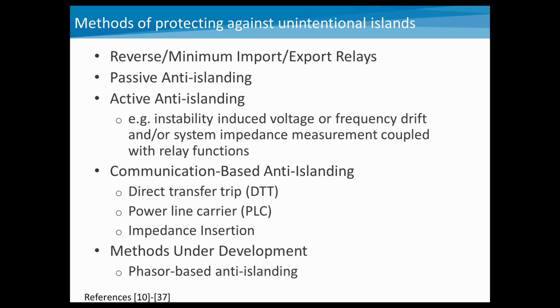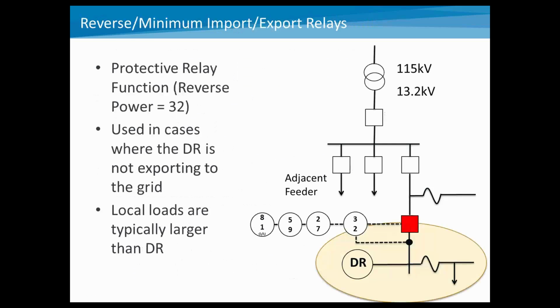So as we move on to additional methods for protecting against unintentional islanding, there's a variety of different types listed here. We'll go through these in more detail. Reverse and minimum import power relays, passive anti-islanding detection methods, active anti-islanding detection methods, communication-based anti-islanding detection methods, and some that are under development. And I'll talk a little bit about each of these. But if you take a look at the references there, 10 through 37 in the back, there's a lot of information available on a variety of different anti-islanding techniques. And I would recommend browsing through these references if you're interested in more details on any one of these.